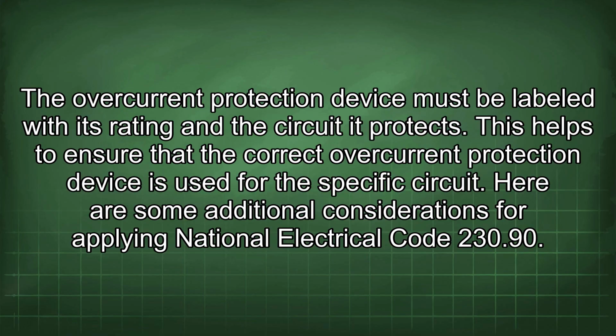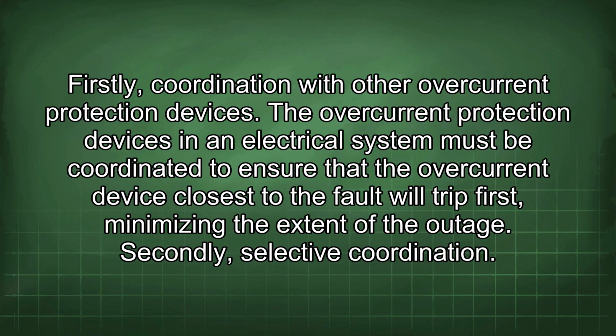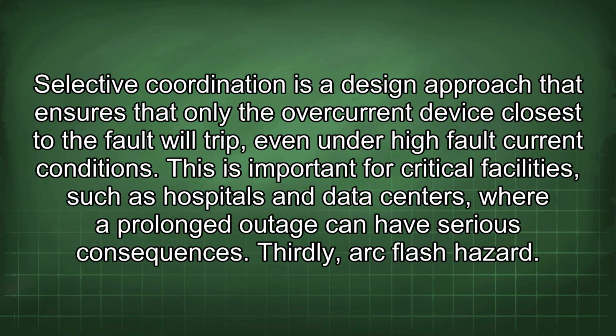Here are some additional considerations for applying National Electrical Code 230.90. Firstly, coordination with other overcurrent protection devices. The overcurrent protection devices in an electrical system must be coordinated to ensure that the overcurrent device closest to the fault will trip first, minimizing the extent of the outage. Secondly, selective coordination. Selective coordination is a design approach that ensures that only the overcurrent device closest to the fault will trip, even under high fault current conditions. This is important for critical facilities such as hospitals and data centers, where a prolonged outage can have serious consequences.